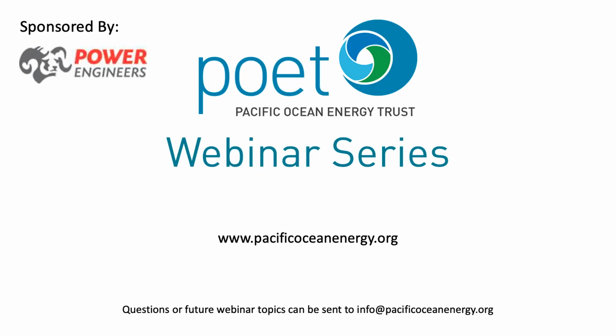Pushing on here: what happens if there's a failure, a rupture, or a break in the transmission cable? In the immediate term, you have protection equipment that will detect the fault and de-energize it in a fraction of a second. That's the fast part. The long part is you have to fix the cable, and that's a challenge. There are a couple of technologies used for it, but frankly that's kind of a nightmare scenario, which is why cables are so thoroughly tested and there's so much rigor put into their manufacture and design, making such faults relatively uncommon. Eventually a cable may wear out, and if it's at the end of its useful life, it would have to be replaced in some fashion.